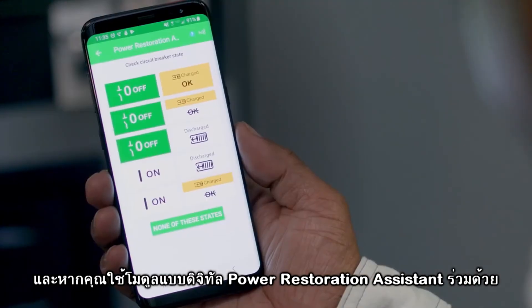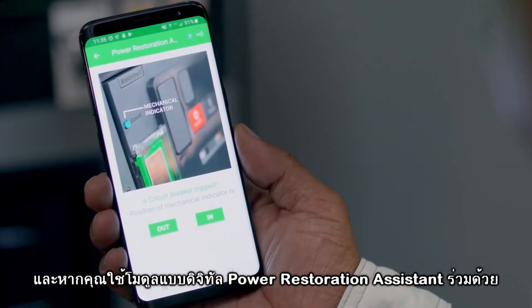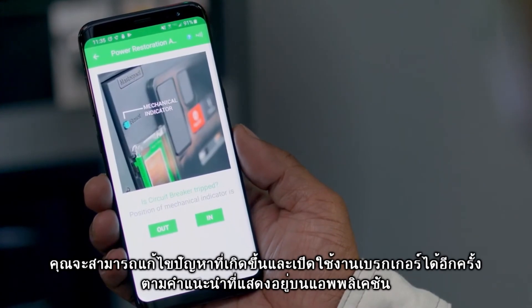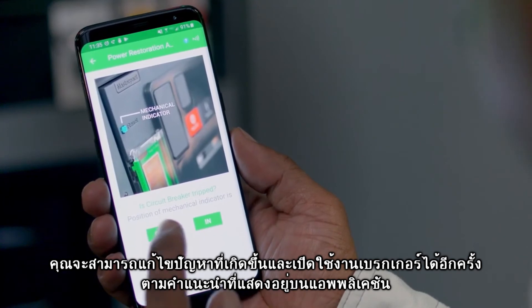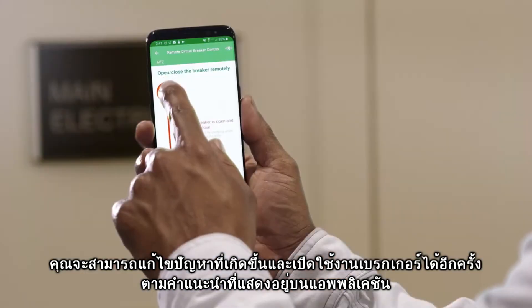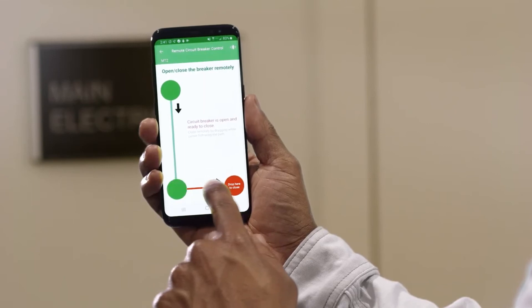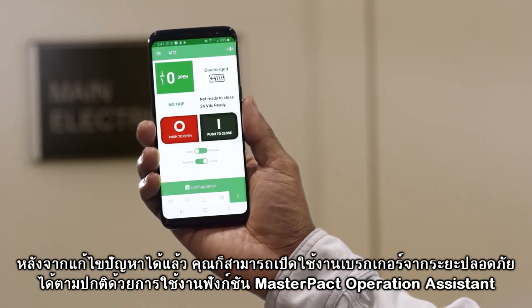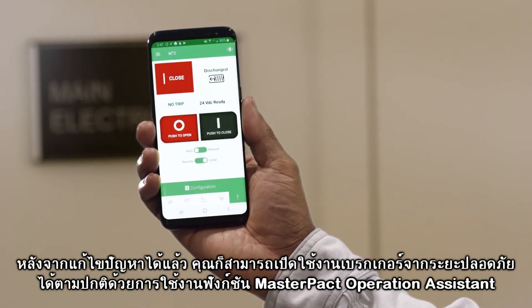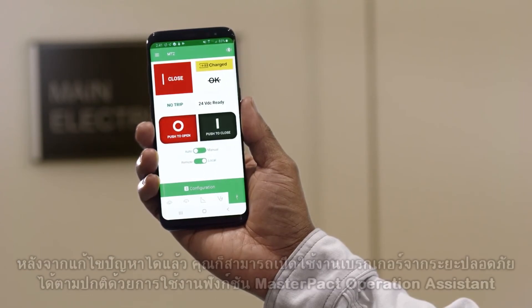Using the MasterPACT MTZ Power Restoration Assistant, you are able to follow specific instructions based on the condition of the circuit breaker, guiding you through the process of re-closing. Once the issue has been resolved, open the operation assistant feature in the app to re-energize the circuit breaker from outside the arc flash zone.